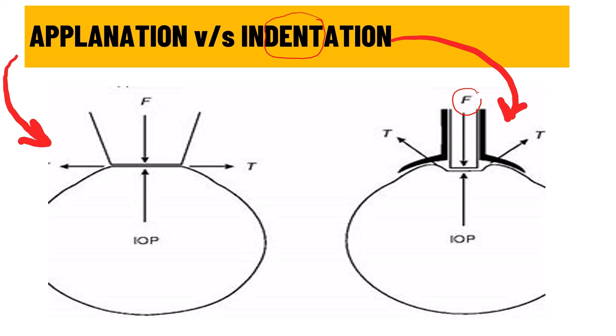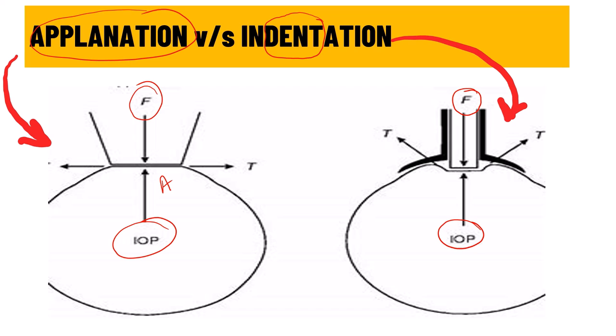In applanation, no localized depression is created. Instead it causes a flattening effect on a particular area of the cornea using a certain amount of force. Once we know this force to applanate or flatten a particular area of the cornea, we can calculate the intraocular pressure. In applanation we are flattening the cornea, whereas in indentation we are creating a depression by depressing the cornea with a certain amount of force.